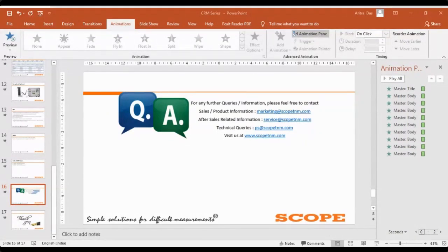You have to refer to the test report of that OEM, the test report of that specific breaker. There you will get the ideal value, what is expected. Based on that, you can correlate whether your contacts are in good condition or require some maintenance. So I hope I could clear up that we cannot say what the correct value of CRM 100 should be. You have to correlate with whatever you have.